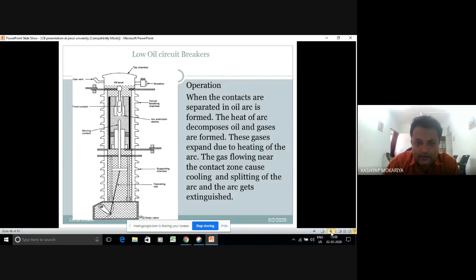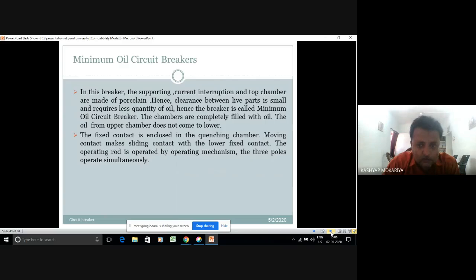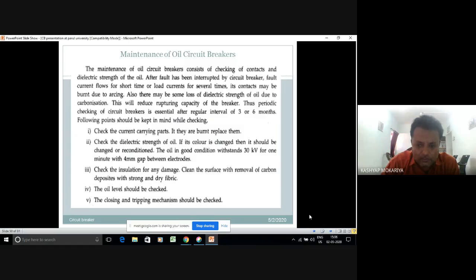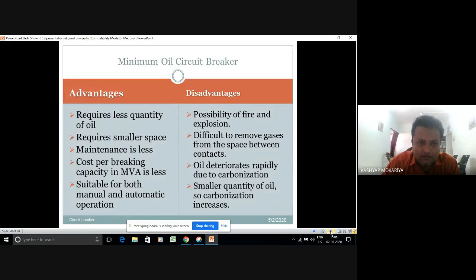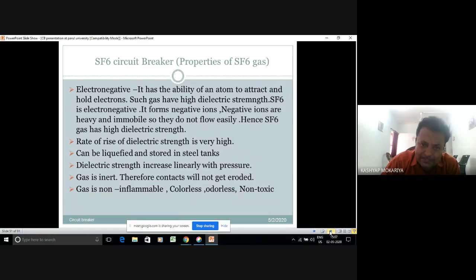Moving now fast, because I was just sharing the industrial experience. So, Minimum Oil Circuit Breaker, as I already explained, the maintenance process I already explained of one of the breaker requires less quantity of oil, requires smaller space, possibility of fire and explosion, oil deterioration rapidly. The big thing I found in MOCB is the oil deterioration or carbonization, that we have to deal with rapidly. We have to send those samples in the testing plant and get all those things.